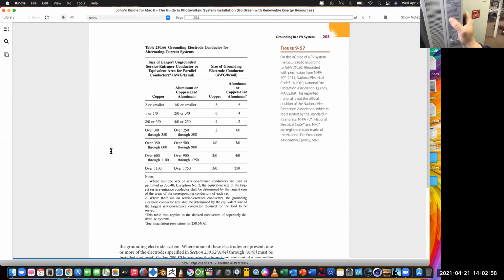For overcurrent protection devices, certified for use with 90 degree Celsius conductors. Remember how we talked about determining whether we can run 60, 75, or 90? This is a first indicator that we could put 90 on it. But that means every connection would have to handle 90, and I doubt that, so we'd most likely go to the 60-degree column anyway. Any questions on that?